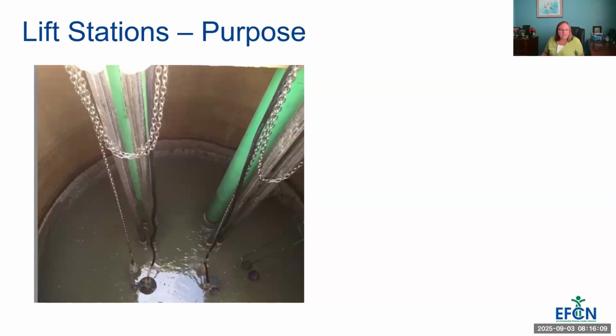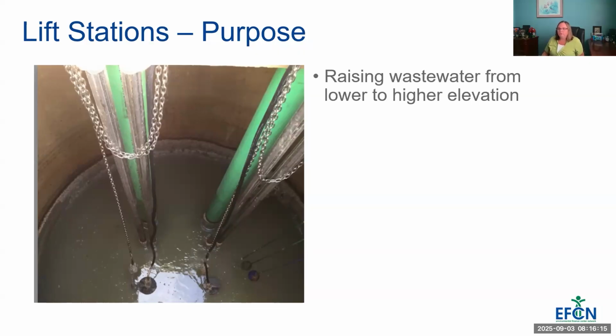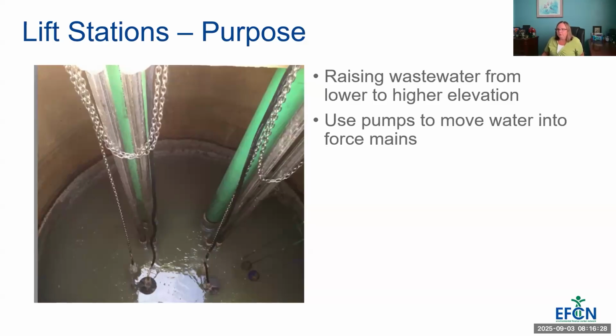The way that some of the training books describe it is pretty close to what you typed out there: raising wastewater from lower to higher elevation, right? So we're lifting water, thus the name, lift station. Sometimes we say pump station because we are pumping water too. We're using pumps to move the water into the force mains. But for the sake of clarity, I think that we prefer to use lift stations for wastewater and pump stations for drinking water. That way we know a bit more about what we're pumping and the reason that we're pumping it. So with lift stations, primarily, we're raising water from one elevation to a higher elevation.